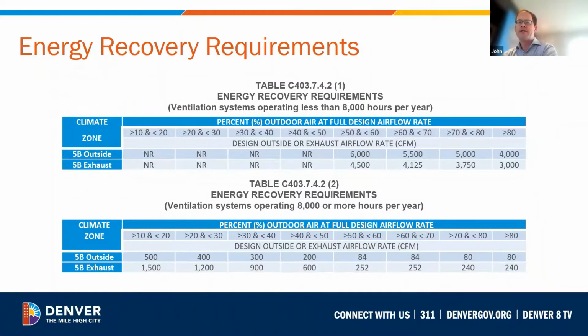The Denver Energy Code has energy recovery requirements for a broad range of commercial buildings. The requirements are more stringent for systems that operate continuously or more than 8,000 hours per year. For systems that operate on a daytime schedule, such as an office or retail building, the requirement varies with the outside air requirement. So the greater the outside air intake amount, the more likely the system is to require energy recovery.